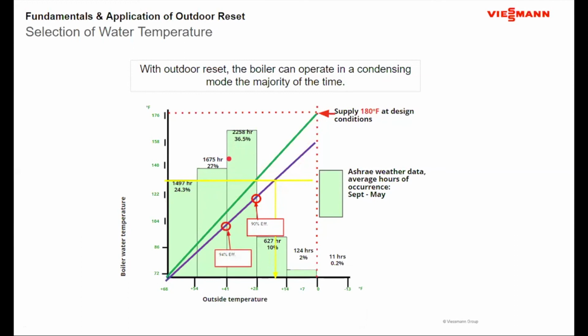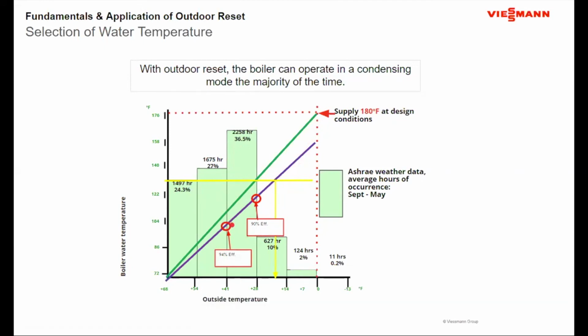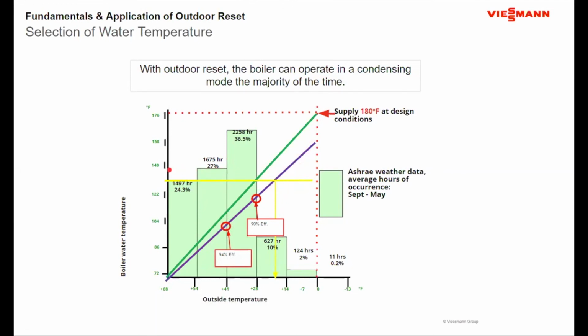If I can bring the temperature down even lower on that heating curve, let's say I can go out at about 110 and come back somewhere near 100. Coming back at 100, that represents about 94% efficient. That boiler can be at least 94% efficient for about 51% of the heating season. So when I start to do outdoor reset control, particularly with condensing boilers, even with baseboard, I still can see really good efficiency numbers, even though under design conditions, the boiler may not condense. And this is really the power of doing outdoor reset with a condensing boiler.